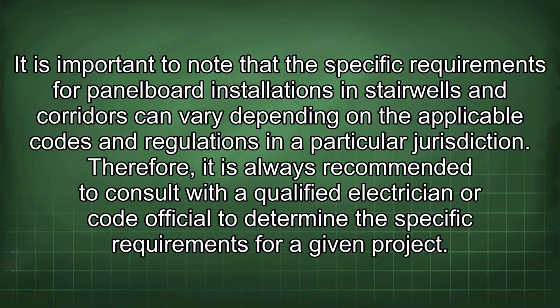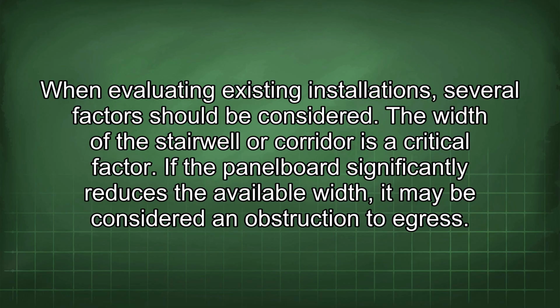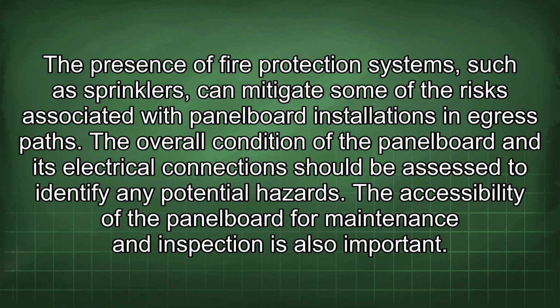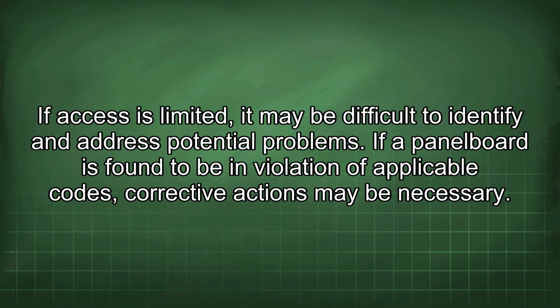It is important to note that the specific requirements for panelboard installations in stairwells and corridors can vary depending on the applicable codes and regulations in a particular jurisdiction. Therefore, it is always recommended to consult with a qualified electrician or code official to determine the specific requirements for a given project. When evaluating existing installations, several factors should be considered. The width of the stairwell or corridor is a critical factor. If the panelboard significantly reduces the available width, it may be considered an obstruction to egress. The presence of fire protection systems, such as sprinklers, can mitigate some of the risks associated with panelboard installations in egress paths. The overall condition of the panelboard and its electrical connection should be assessed to identify any potential hazards. The accessibility of the panelboard for maintenance and inspection is also important. If access is limited, it may be difficult to identify and address potential problems.